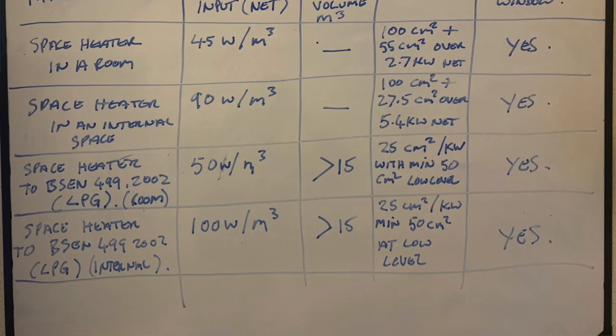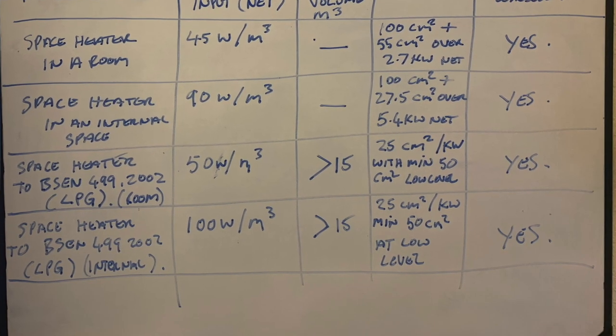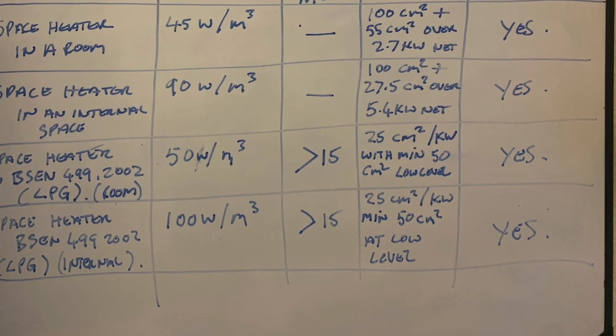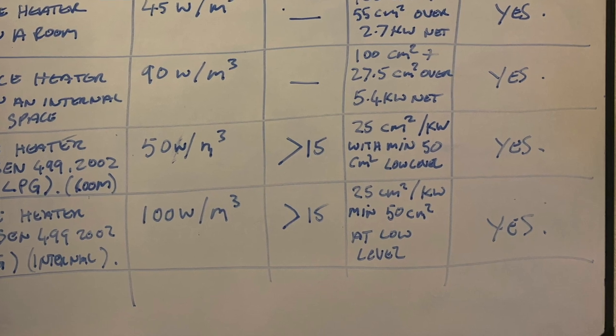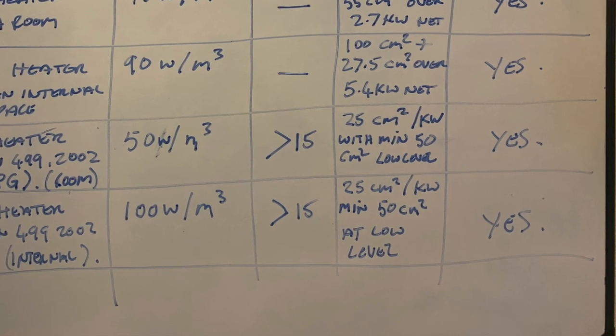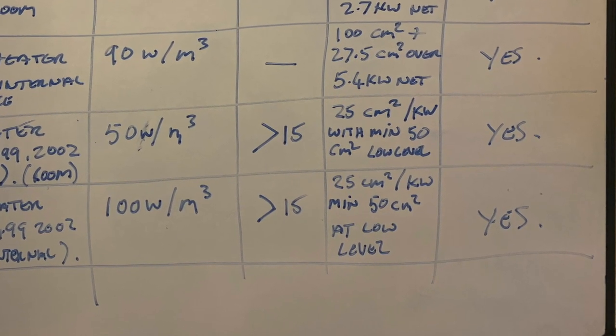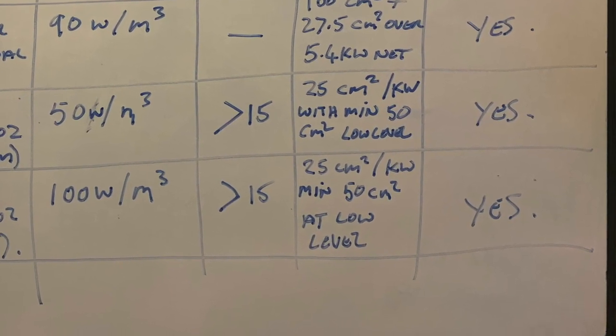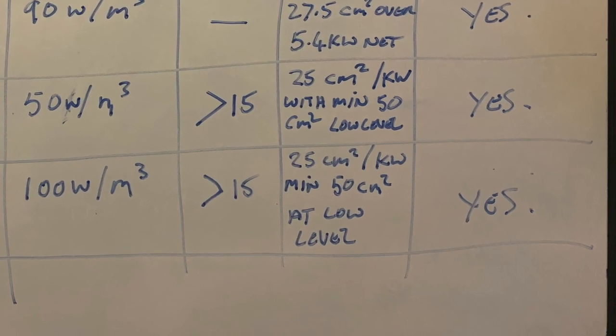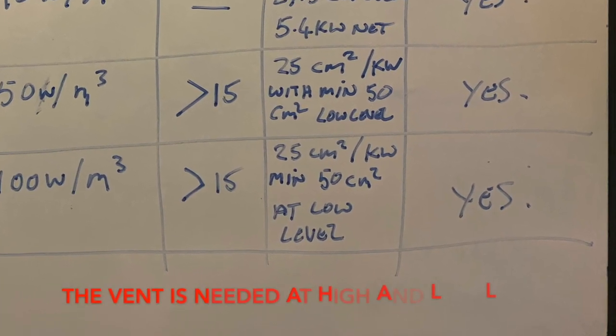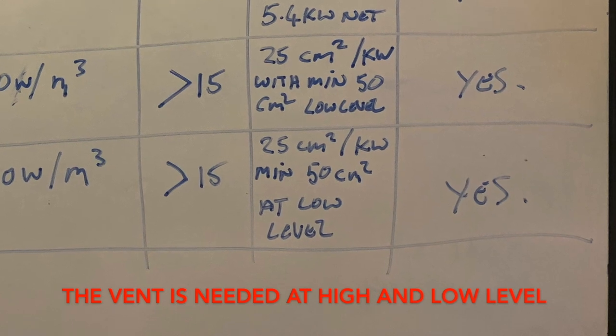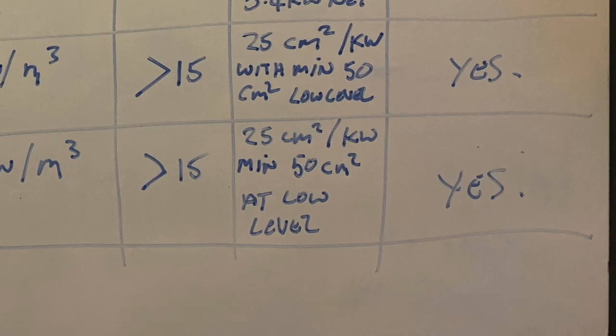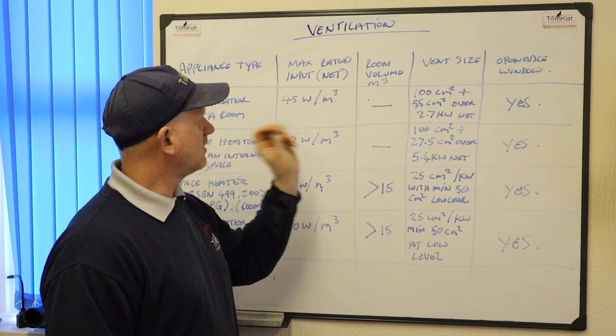For space heaters to BS EN 499:2002 — again LPG — in an internal space, it's 100 watts per metres cubed, the room volume must be greater than 15 metres cubed, and again it's 25 centimetres squared per kilowatt with a minimum of 50 centimetres squared at high and low level, plus an openable window. That's what we need to be working to for ventilation.